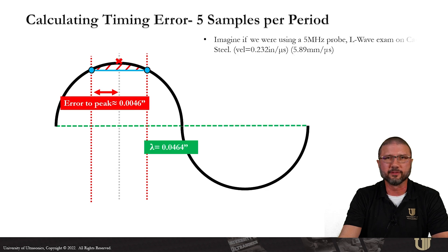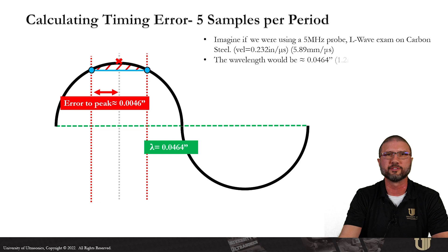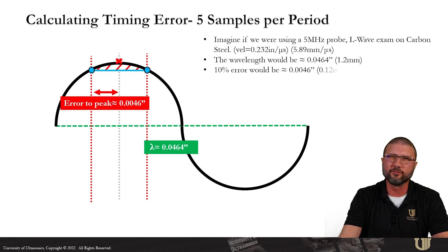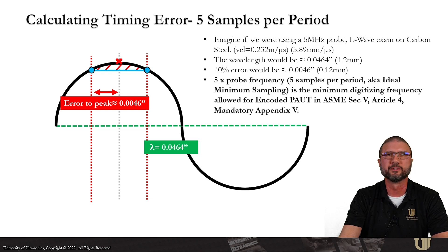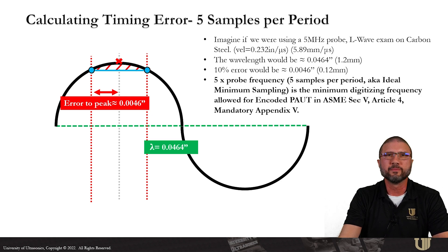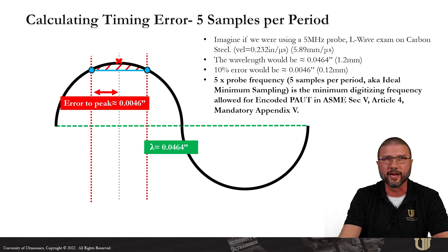For a 5 megahertz L-wave exam on carbon steel, that 10% error equals about four or five thousandths of an inch, about 0.12 millimeters — really small and getting very close. Five times the probe frequency is actually the minimum digitizing frequency allowed for encoded phased array in ASME Section 5, Article 4.